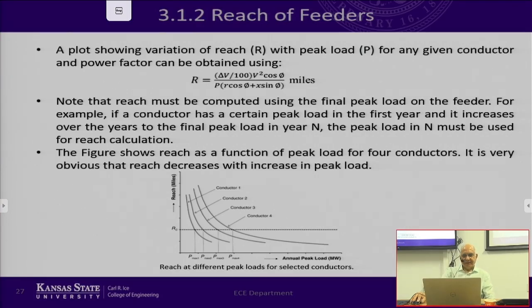If you want a common reach, it's because we are given a system to build: you have a substation, and the maximum distance you have to go is, say, 5 kilometers. That distance is known to us, we can go that far. So now we want to decide which size of conductor to use. There are two factors, cost and reach, so this is a balance between the two.